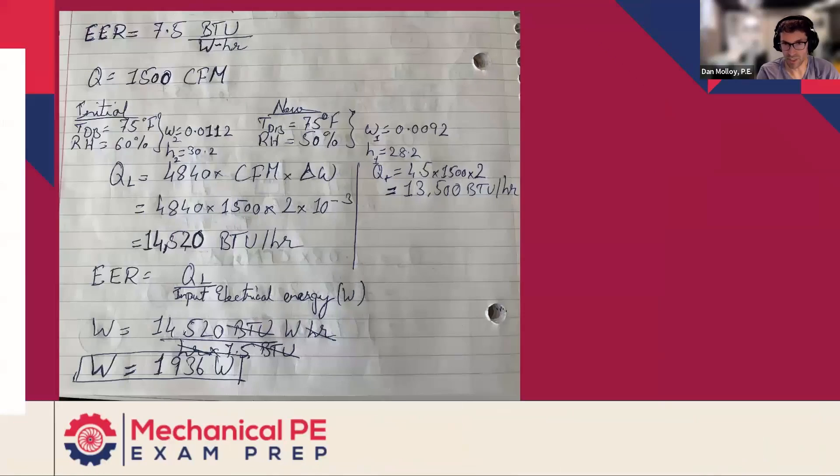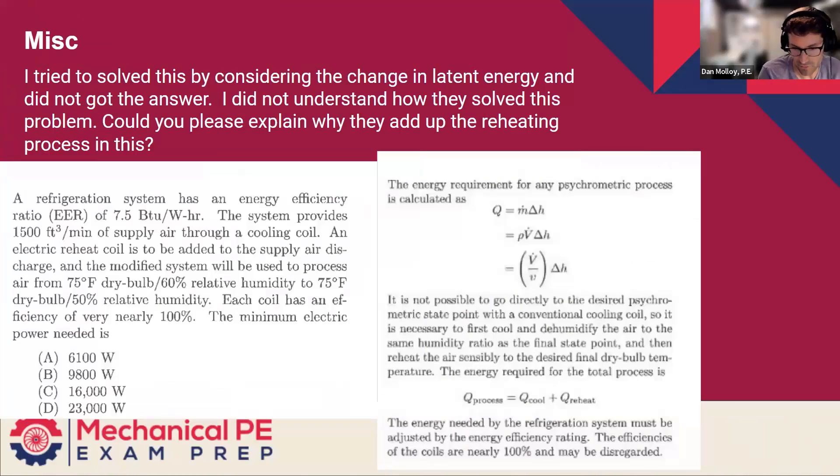So this is a long solution, but it's not actually that hard of a concept. We can cover it pretty quickly. So refrigeration system has an energy efficiency EER of 7.5 BTU per watt hour. The system provides 1500 CFM of supply air through a cooling coil. An electric reheat coil is to be added to the supply air discharge, and the modified system will be used to process air from 75 dry bulb 60% RH to 75 dry bulb 50% RH. Each coil has an efficiency of very nearly 100%. The minimum electric power needed is what?